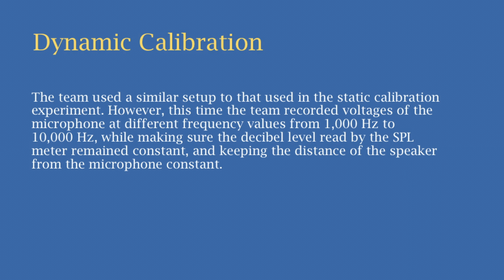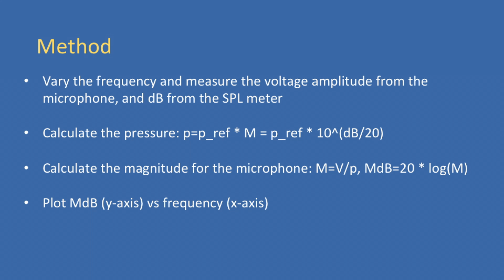This time the team recorded the voltage of the microphone at frequencies varying from 1000 Hz to 10,000 Hz, while making sure the decibel level read by the SPL meter remained constant and keeping the distance of the speaker from the microphone constant. The steps of data analysis for dynamic calibration are shown here.